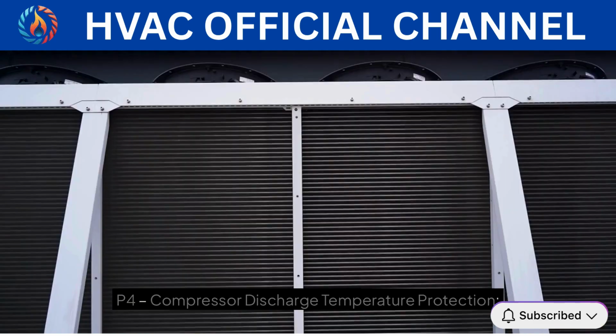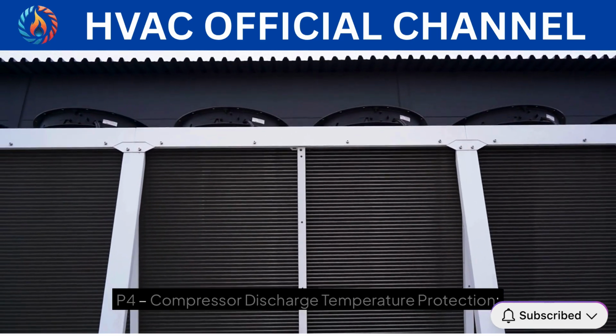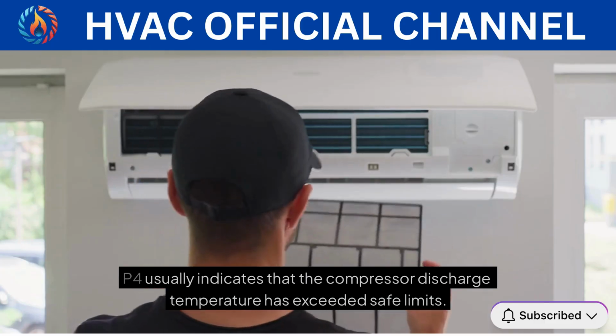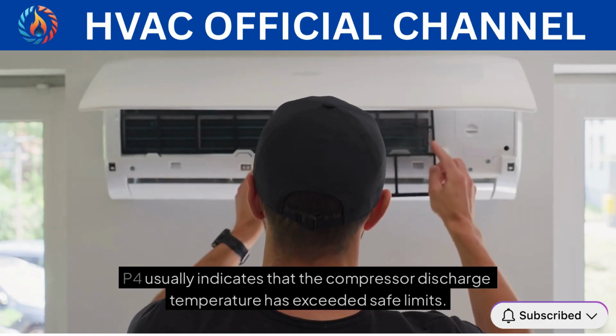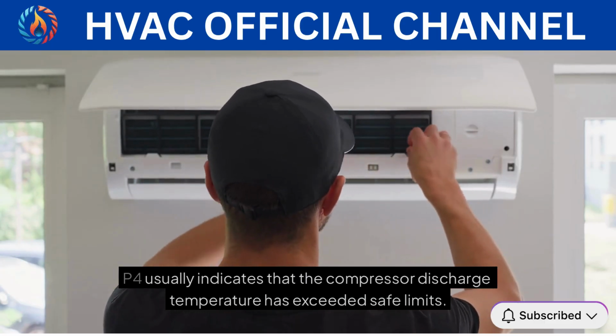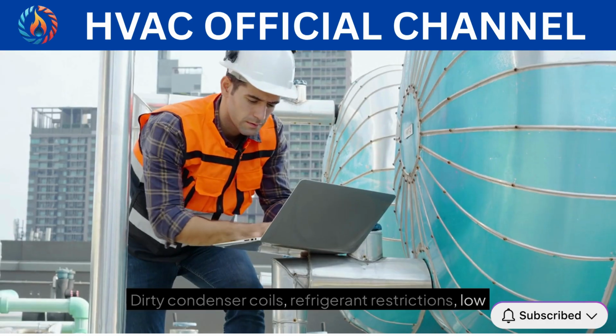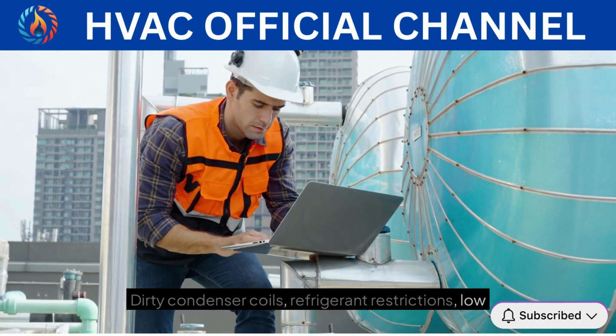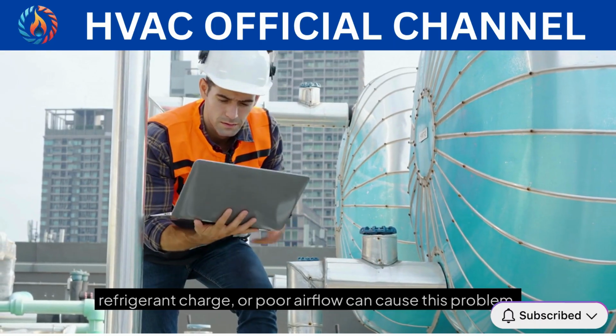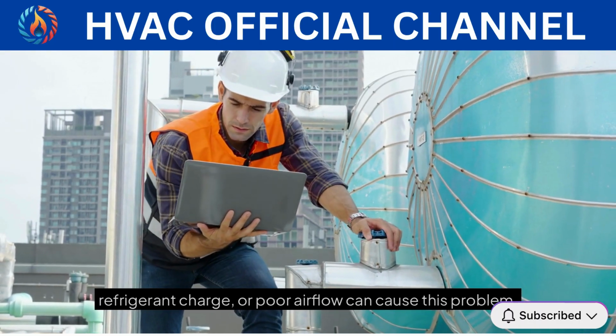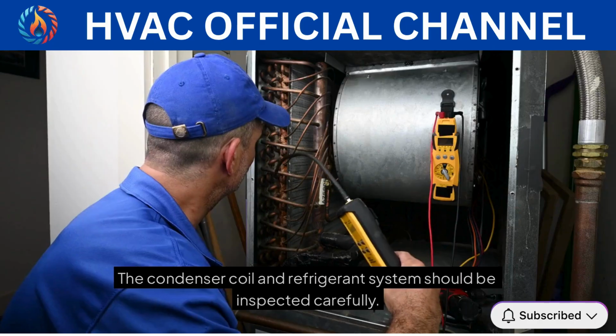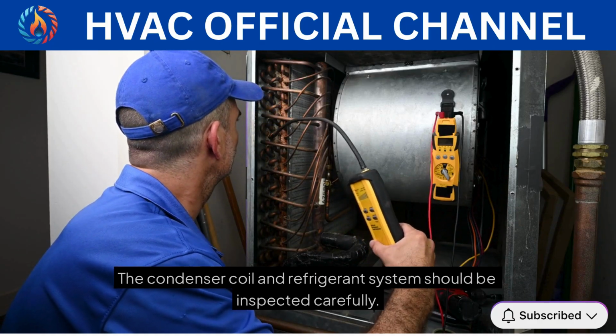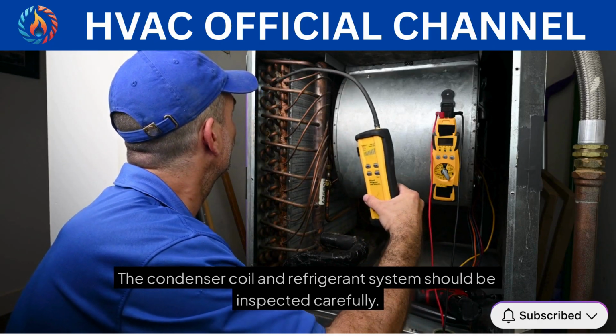Error code 9, P4, compressor discharge temperature protection. P4 usually indicates that the compressor discharge temperature has exceeded safe limits. Dirty condenser coils, refrigerant restrictions, low refrigerant charge, or poor airflow can cause this problem. The condenser coil and refrigerant system should be inspected carefully.